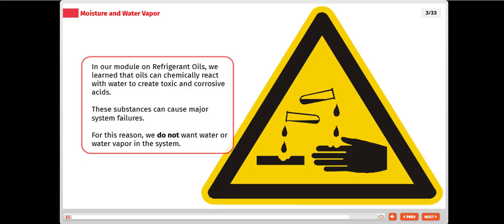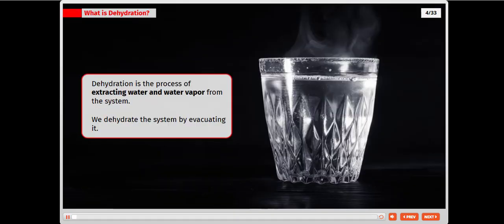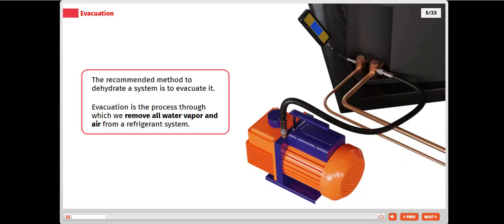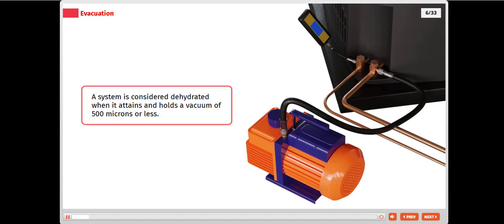Dehydration is the process of extracting water and water vapor from the system. We dehydrate the system by evacuating it. The recommended method to dehydrate a system is to evacuate it. Evacuation is the process through which we remove all water vapor and air from a refrigerant system. A system is considered dehydrated when it attains and holds a vacuum of 500 microns or less.